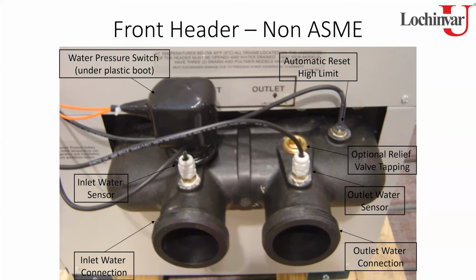Yeah, this heat exchanger, I don't want to say it's weird, but it's a lot different from other copper style heat exchangers that we have, because you're not seeing a full pass through the heat exchanger. You're not seeing water coming in the inlet, passing through 4 passes in the heat exchanger and coming straight out. So it's almost like the delta T that you're seeing is false, because it's a mixed temperature.